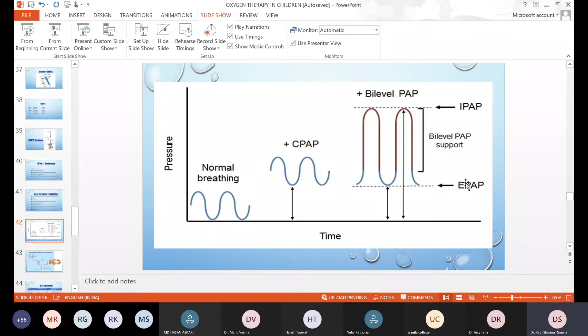Then the second is bi-level pressure. Here we are giving two pressures to the patient. The one is again the expiratory pressure. Here we called it CPAP, here we call it EPAP. The pressure is the same, EPAP and CPAP. This is a continuous pressure applied to the system. And then the other pressure is IPAP. This much pressure we apply during the inspiratory phase. This is inspiratory positive airway pressure, and this is expiratory positive airway pressure. We give this during expiration and this during inspiration.